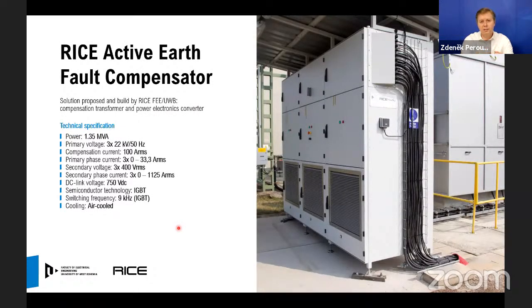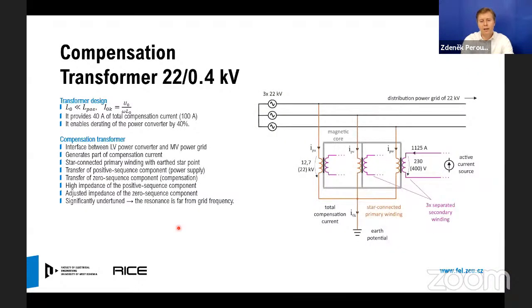Based on this idea, we developed in Rice a first prototype of this device having the rated power of 1.35 megavolt amps. This prototype is dedicated for installation in the power grid with the rated voltage of 22 kV and offers a compensation current of 100 amps RMS. The device has two main components. It is a compensation transformer, and in our case, in the first generation, a low voltage converter, which is connected to the secondary winding of this transformer.